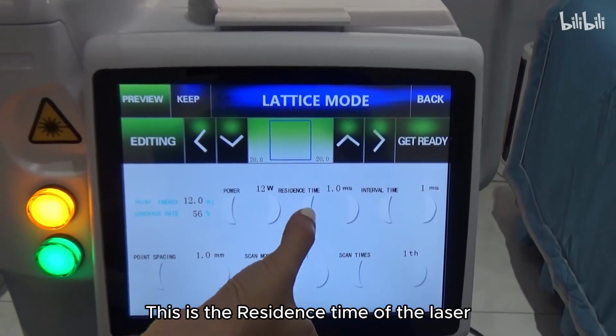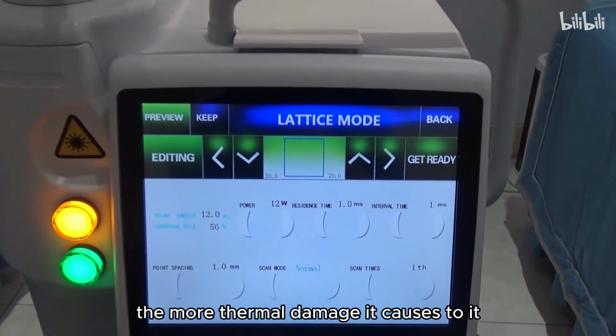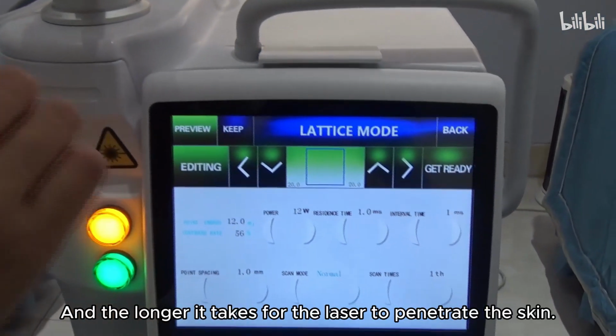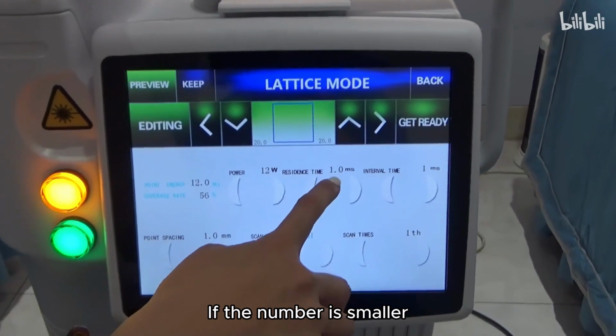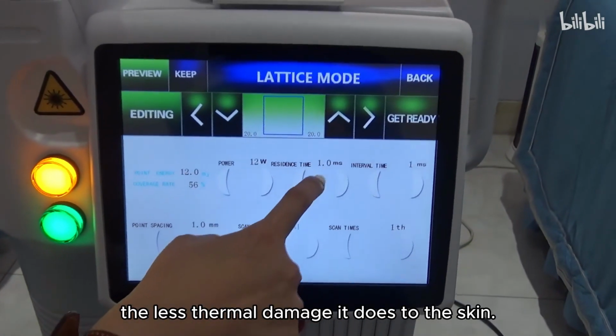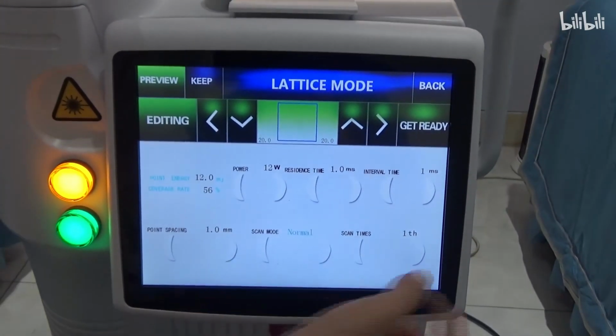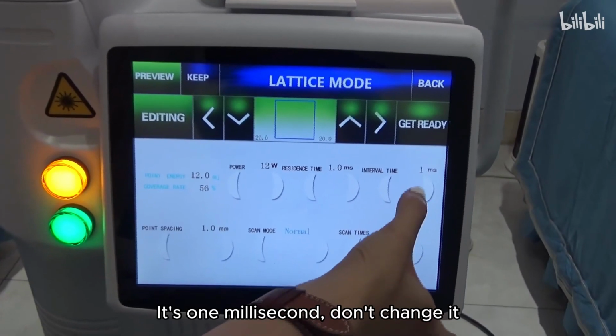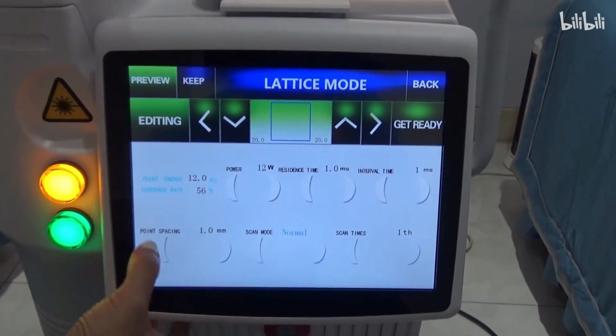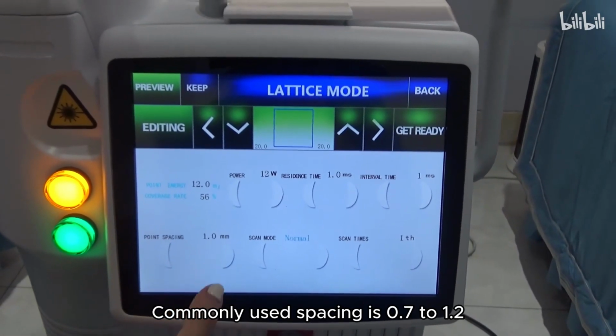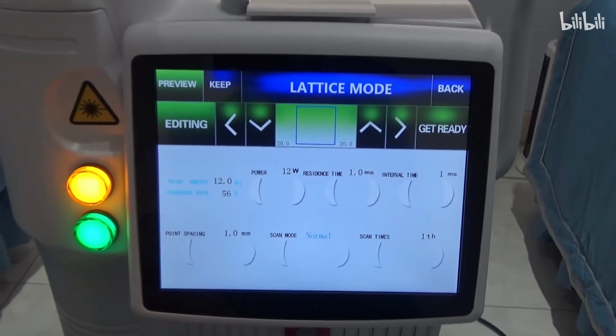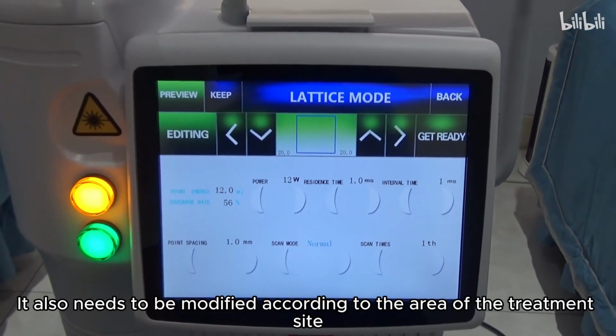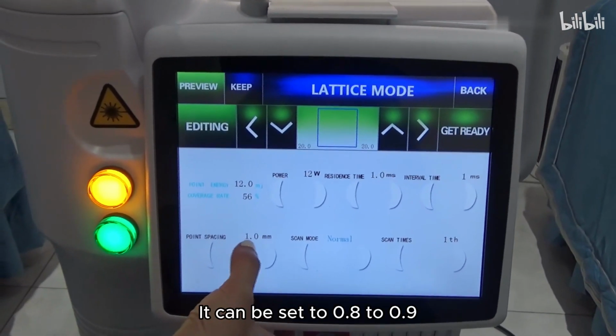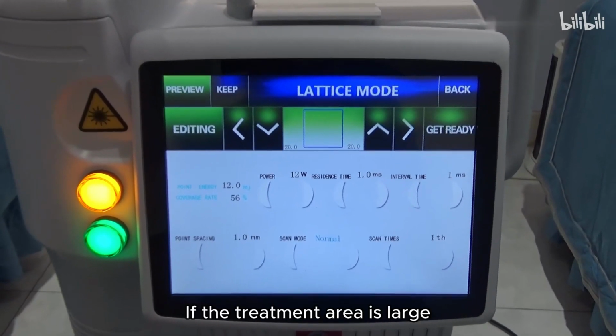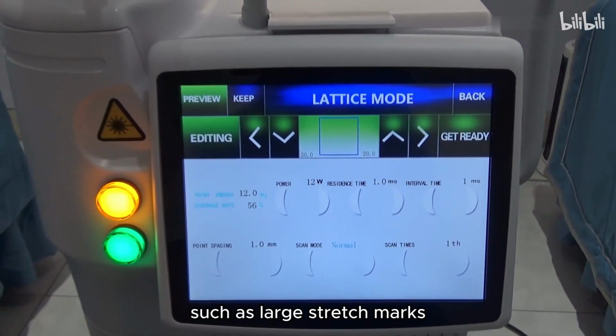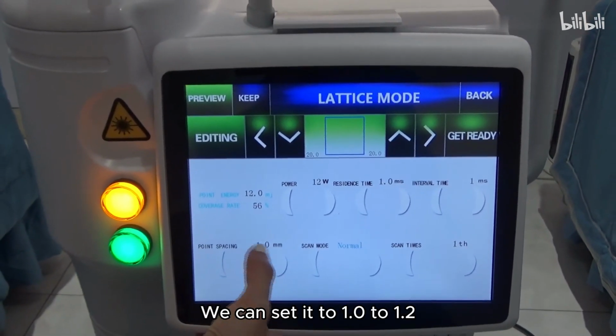This is the residence time of the laser. The longer the laser stays on the skin, the more thermal damage it causes to it, and the longer it takes for the laser to penetrate the skin. If the number is smaller, the less thermal damage it does to the skin, so this number is usually 1. This is the laser's interval time. It's 1 millisecond, don't change it. This is the laser's point spacing. Commonly used spacing is 0.7 to 1.2. It also needs to be modified according to the area of the treatment site. If the treatment area is small, it can be set to 0.8 to 0.9. If the treatment area is large, such as large stretch marks, we can set it to 1.0 to 1.2.